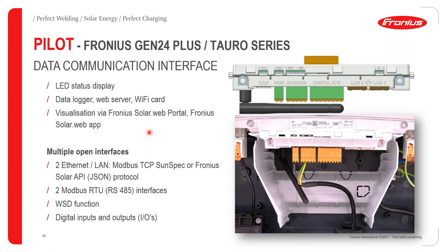Like the Data Manager, the Pilot can achieve visualization via the Fronius SolarWeb portal and app. It has multiple open interfaces — unlike the Data Manager which has one, it has two Ethernet ports for Modbus TCP connection, two Modbus RTU ports, and digital input and output ports, as well as a WSD wired shutdown function.